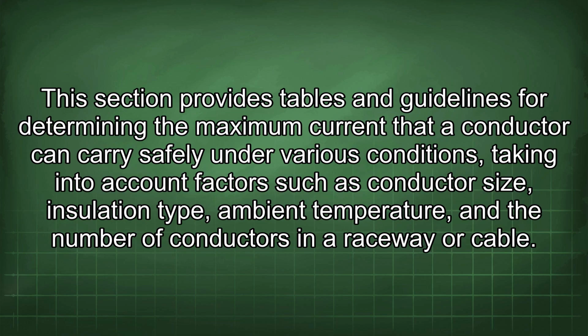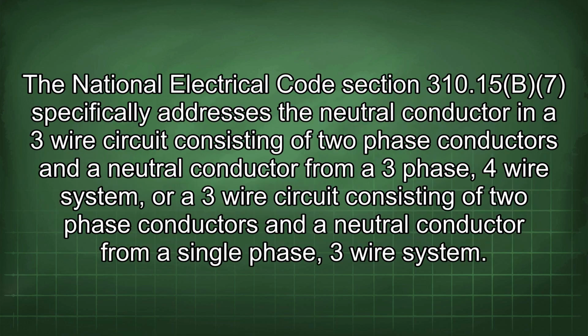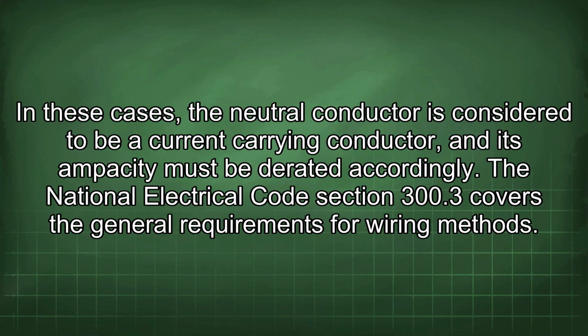This section provides tables and guidelines for determining the maximum current that a conductor can carry safely under various conditions, taking into account factors such as conductor size, insulation type, ambient temperature, and the number of conductors in a raceway or cable. National Electrical Code Section 310.15(B)(7) specifically addresses the neutral conductor in a 3-wire circuit consisting of 2 phase conductors and a neutral conductor from a 3-phase 4-wire system, or a 3-wire circuit consisting of 2 phase conductors and a neutral conductor from a single-phase 3-wire system. In these cases, the neutral conductor is considered to be a current-carrying conductor, and its ampacity must be derated accordingly.